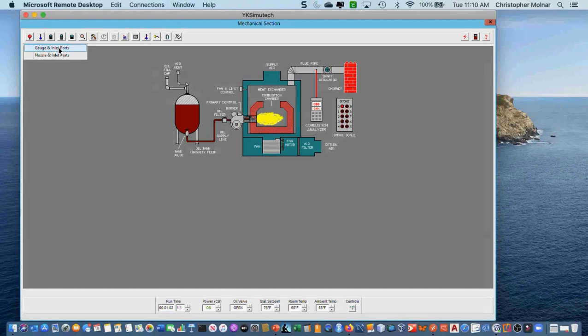Okay, I could put an oil valve on. I could put a gauge on the nozzle and inlet ports. Okay, so if I wanted to put an oil gauge on here, I can see what my oil pressures are. My pressure is 100 psi. My vacuum is basically 0 inches.